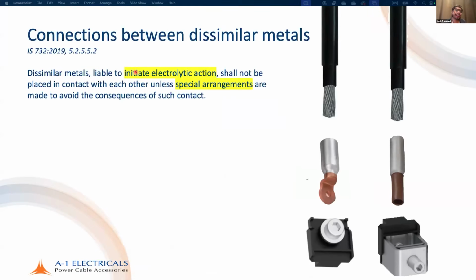Now, when we talk about connections between dissimilar metals, the requirements are given in 5.2.5.5.2. Aluminum conductors are widespread in India, and the terminal connections are often brass or copper. Dissimilar metals, these are metals that are different, are liable to initiate electrolytic action, and they shall not be placed in contact with each other unless special arrangements are made to avoid the consequence of such contact. This special arrangement, for example, may be this lug, which is a bimetallic lug that ensures there is no electrolytic corrosion.